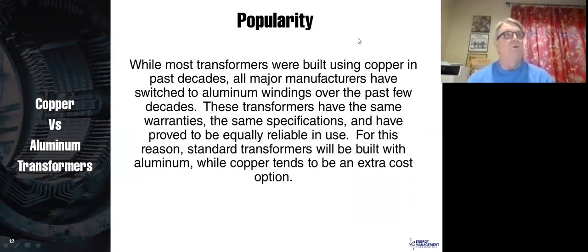Now, popularity. I was the director of engineering for Geneva Steel. And before that, I was a district engineer with Westinghouse. Westinghouse at the time was a huge manufacturer. They sold out mostly to other manufacturers, mostly to Eaton and to ABB. But they were a huge manufacturer, and there came a period of time when aluminum was cheaper than copper. And so Westinghouse moved all of their standard distribution transformers to aluminum. So did GE, so did Cooper. Everybody pretty much went to aluminum.